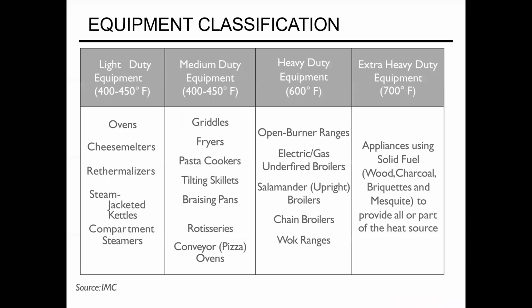So, cooking equipment classifications. This is a list I took from the IMC. There are similar ones in the ASHRAE handbook and also some of the other ASHRAE standards. Like I said, when you're sizing a hood CFM, it's based on the appliance with the heaviest duty rating. You could have nothing but ovens, and then an open burner range. Ovens and a broiler would be a heavy duty hood.